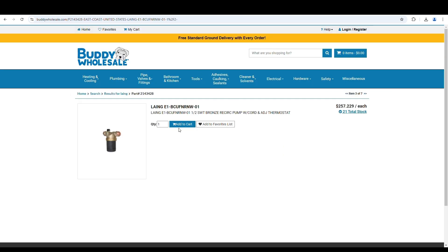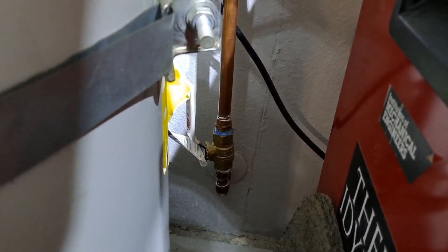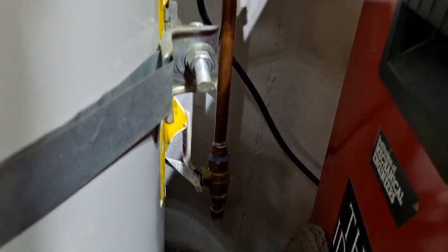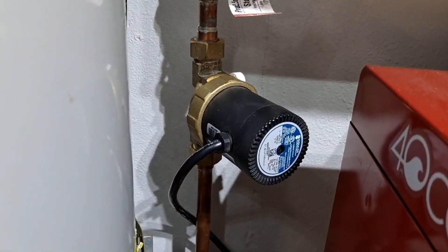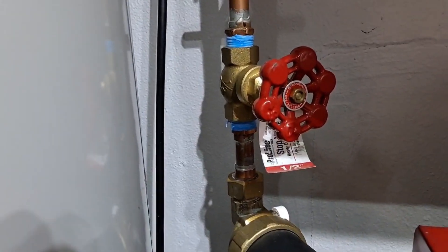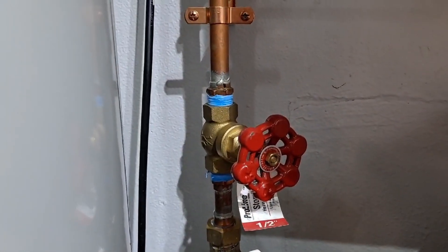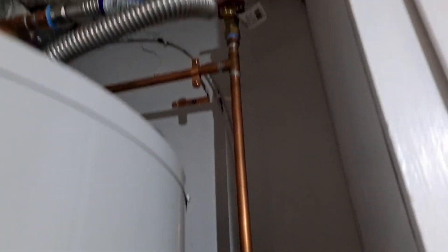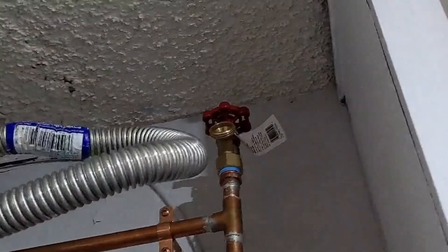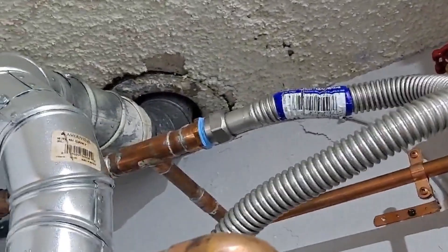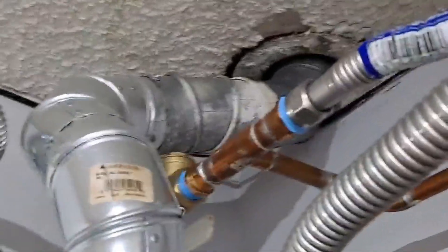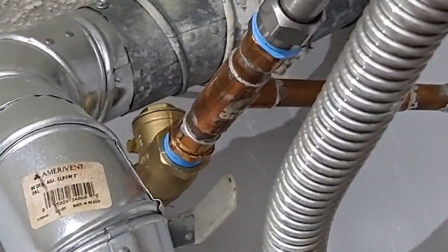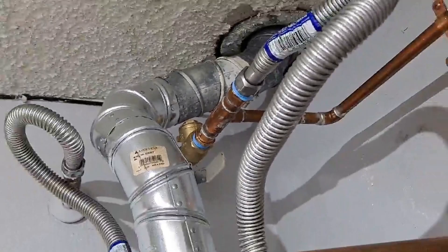So following the instructions from the pump manual, I installed the valve just on the inlet. Here's the pump. And then I put this valve in here because, in order to control the flow, I'll go into that in a little bit later. And then following up to the top with the vent valve on the top, across and into the cold water inlet. And then you can just about see back there, right there is a check valve on the cold water coming into the hot water heater.